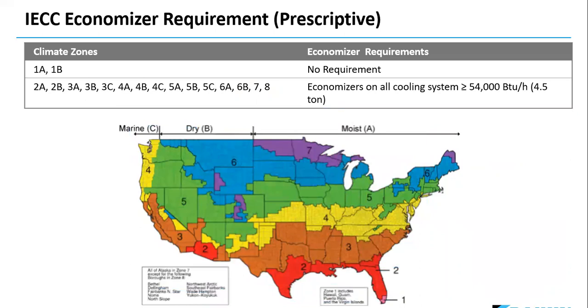One of the reasons for using the prescriptive path is to help determine whether or not economizers will be needed. Typically a lot of engineers will use the ASHRAE 90.1 path. That prescriptive path allows us to make the installation of the system easier by eliminating the economizer requirement. You can see that in Texas, we actually fall in zones that do call for economizers, particularly the brown area that you see around the state of Texas on the screen. So this prescriptive method is used quite frequently.